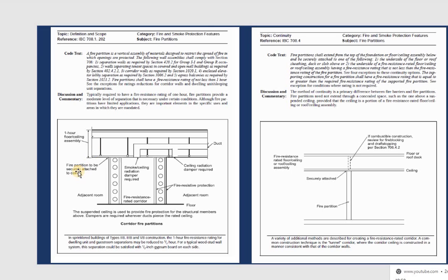All material is one hour. The fire partition must be securely attached to the ceiling — from the floor up to the ceiling, secured at the room-to-room connection. If you have a fire partition and there is concealed space between the ceiling and floor, to connect between them you should use combustible construction with fire blocking or draft stopping, qualified for the required fire rating. All material between spaces must be fire resistant for the floor and roof assembly.